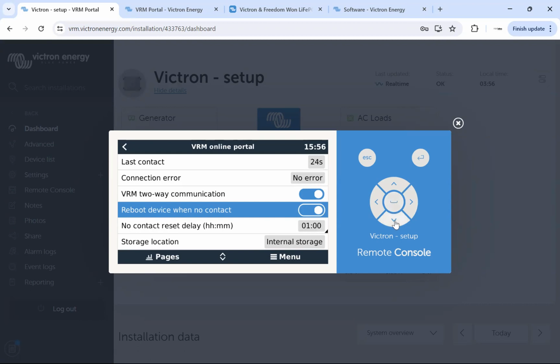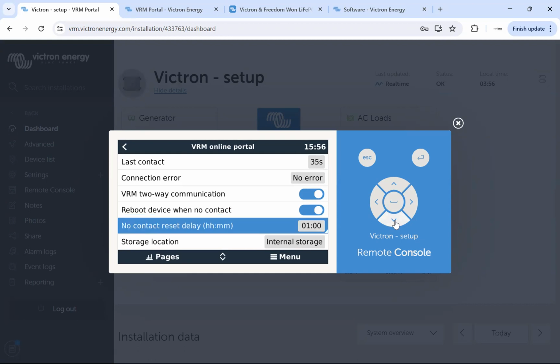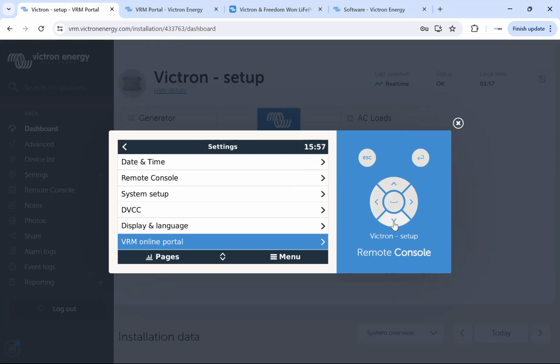You want the system to be logging. You don't want the router to just boot it off because something else is going on, like 3 people streaming Netflix or something. So I set that at reboot for 1 hour. If it's got no communication with the VRM online portal, then it will reboot this GX device. It won't kill the power to the system or anything like that. It'll just reboot the GX device, and that reboot will then make the internet router see the GX device online and then connect to it again. So that's sometimes good if you've got issues with it dropping offline. I just enable it out of habit.